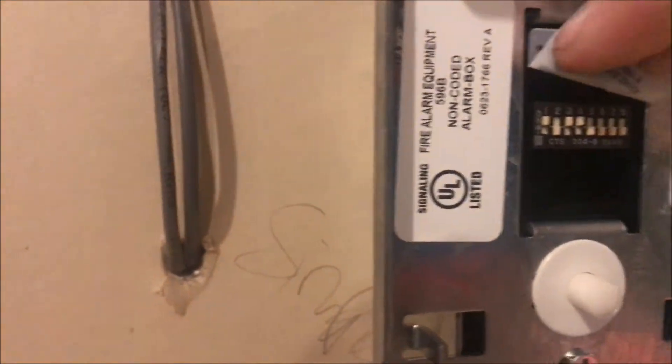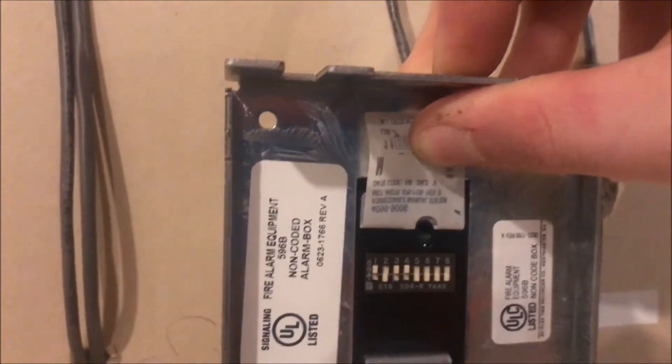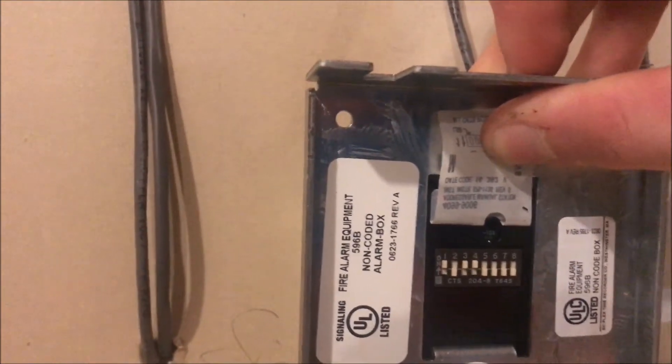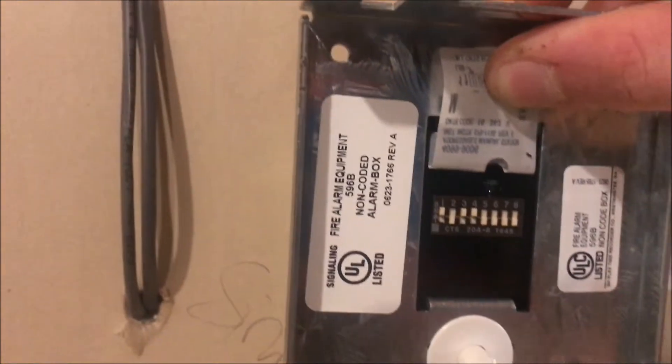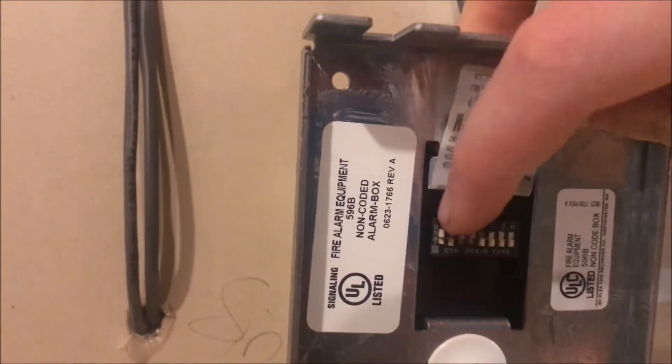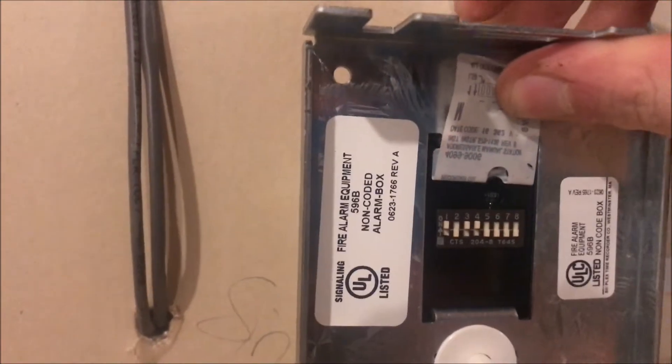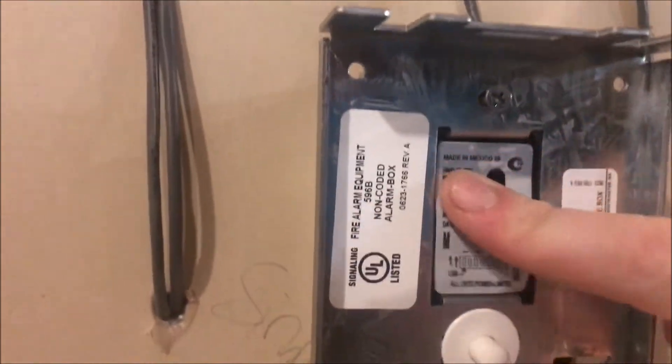So switch one is up, that means one. Switch three is up, that means four. Switch four is up, that means eight. So four plus eight is 12, plus one is 13. It just doubles each time - that's how binary works. So I have it set as point 13 on the address card.